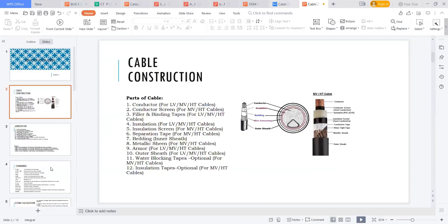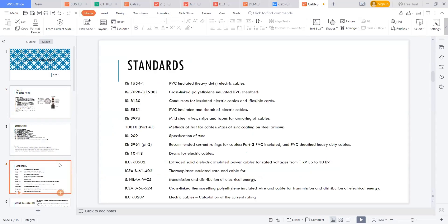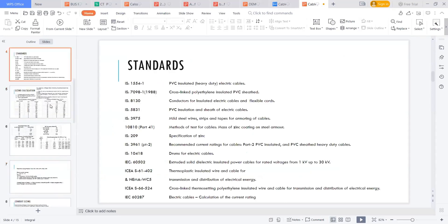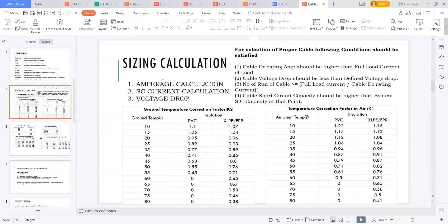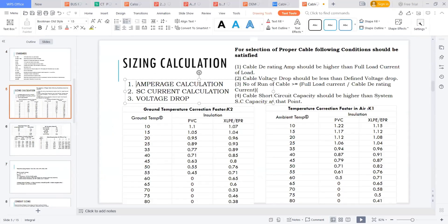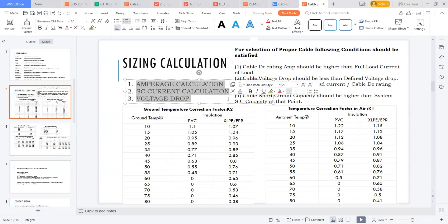The next one is the sizing of the cable. Sizing of the cable will be done with three things: one is the amperage calculation, the other one is the short-circuit calculations, and the other one is the voltage drop. This will tell us the size of the cable required.